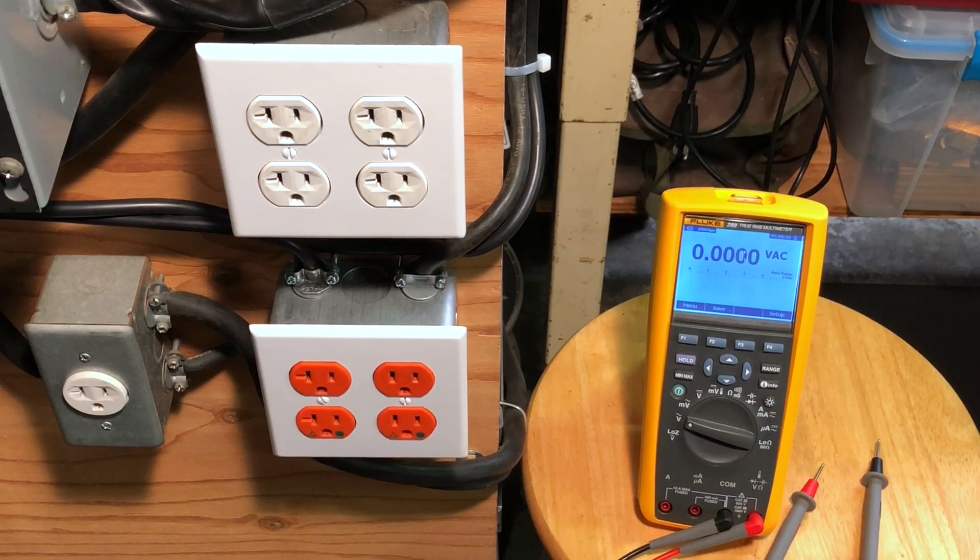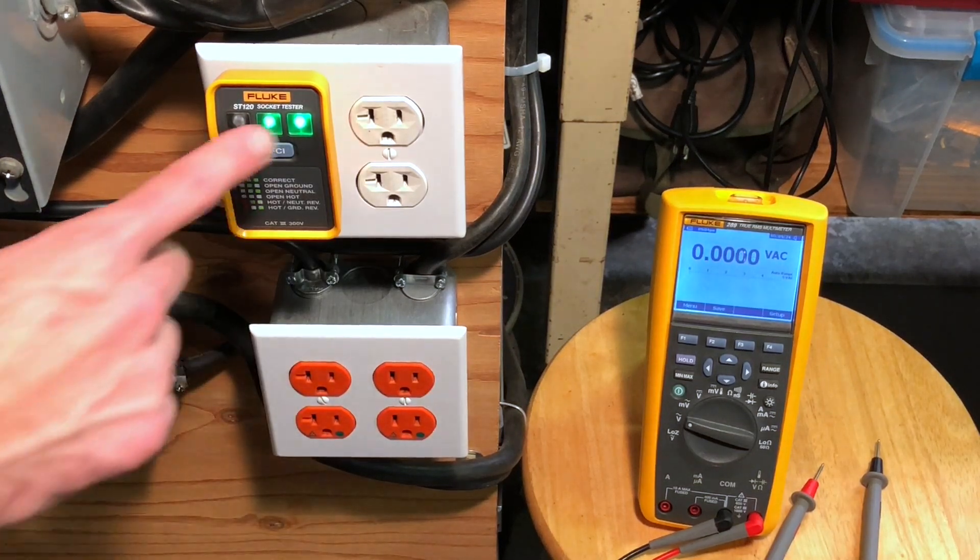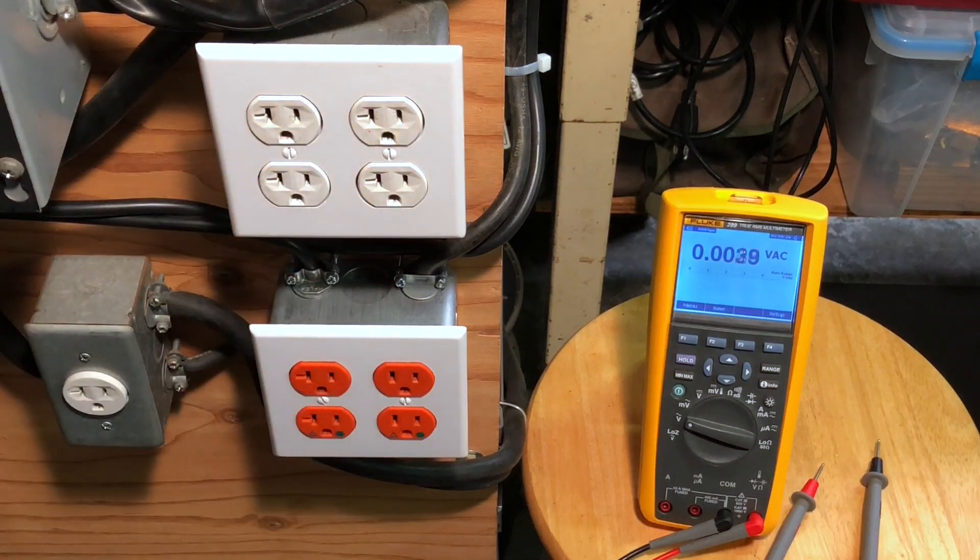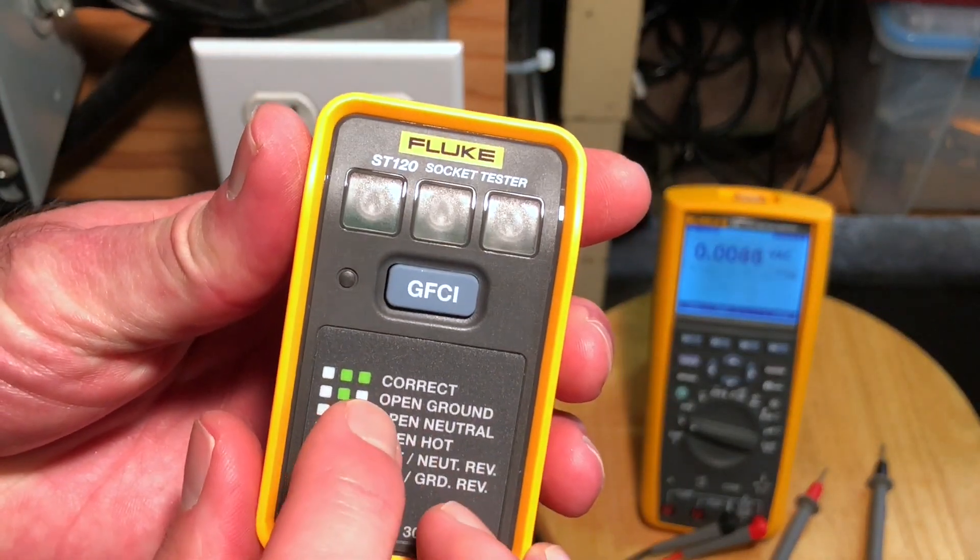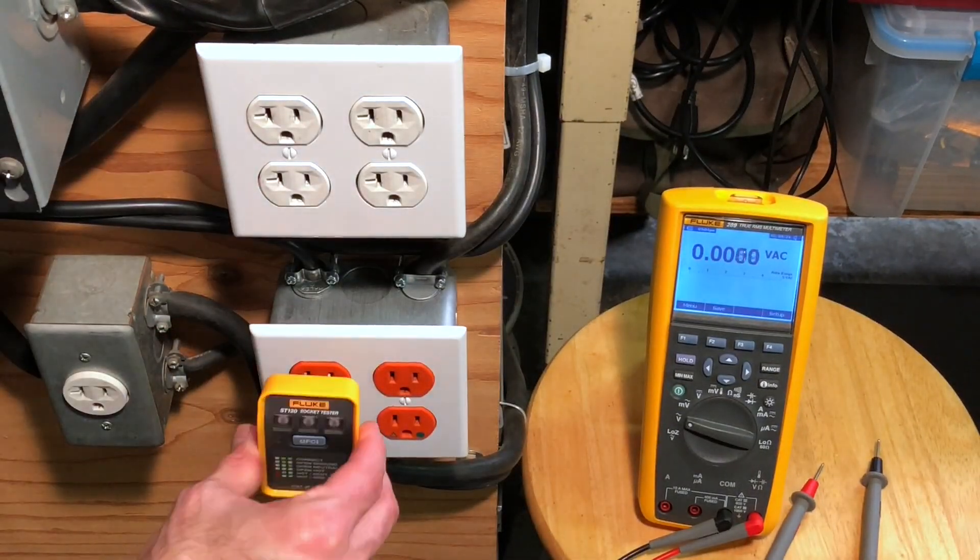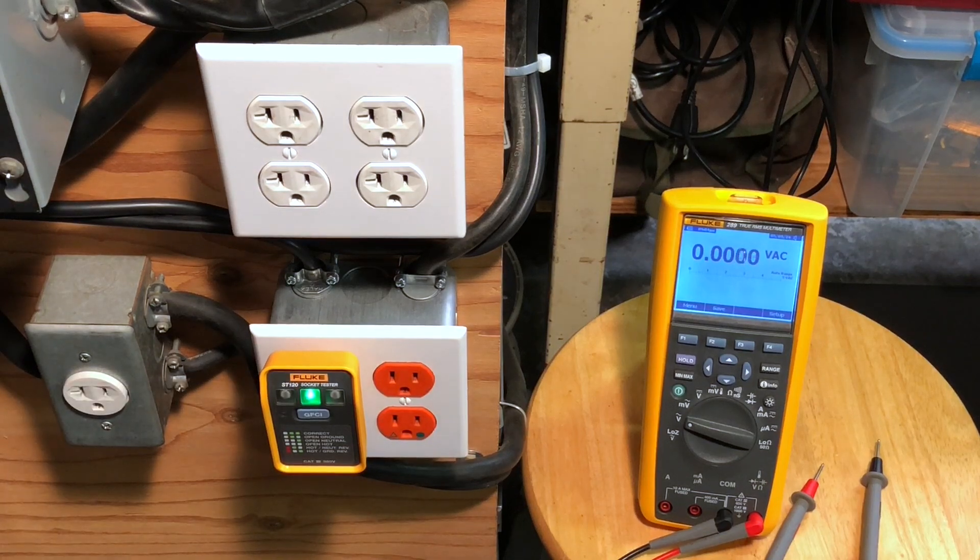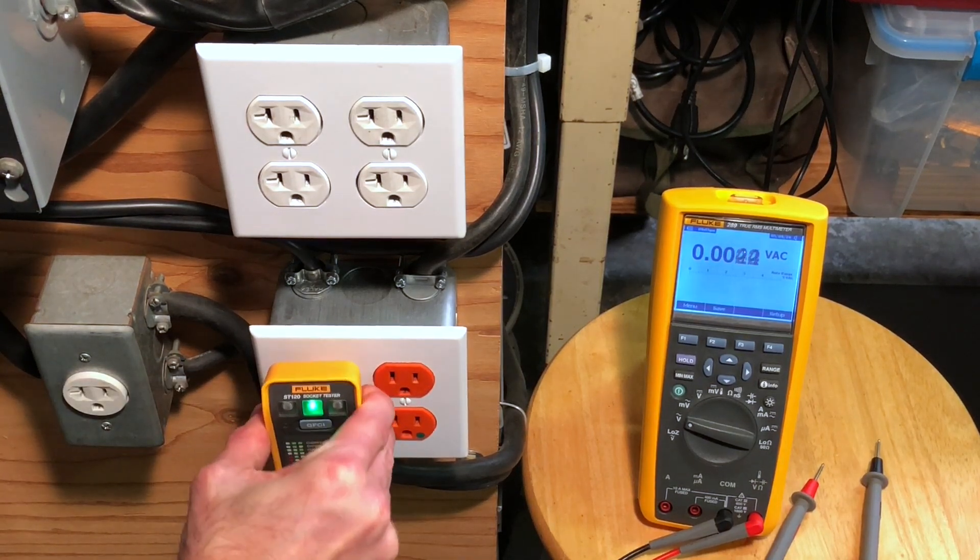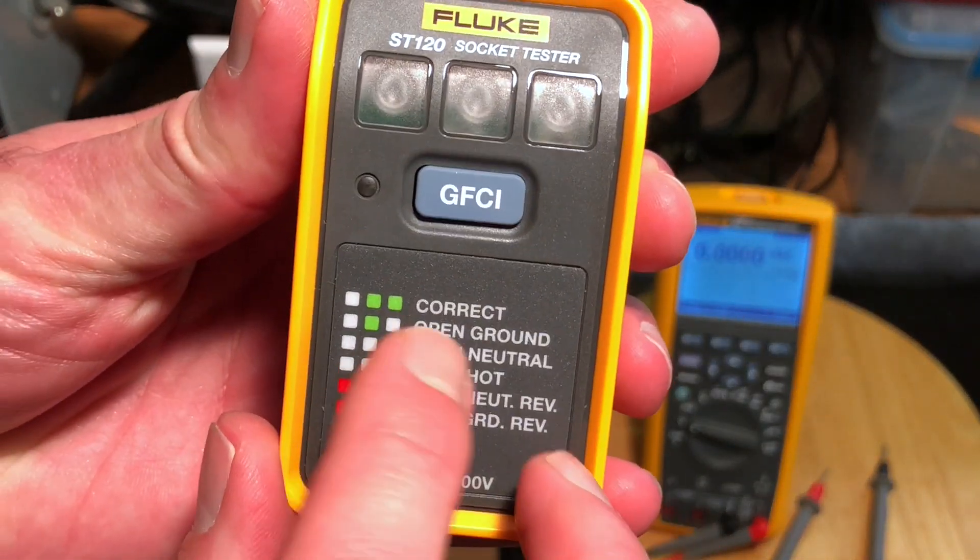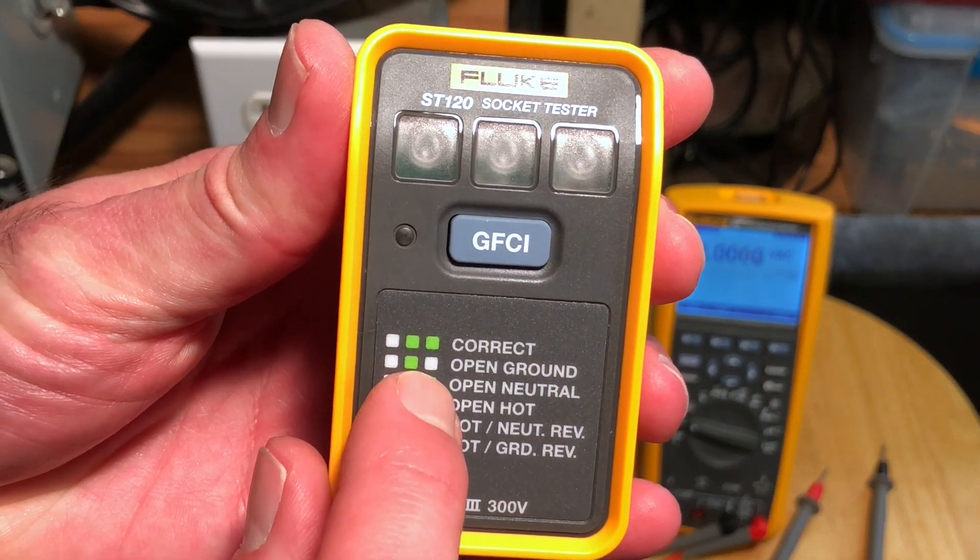Let's plug that in. You can see these are all energized. Down here, same thing, isolation transformer is on. This outlet here is part of an AC power source, a completely different piece of equipment. I have my outlet tester. This will just confirm the wiring configuration. If I plug that in, you can see those two green lights are on and this light is off. If we take a look at the chart, two green lights means correct wiring, no issues. If I plug it into the isolation transformer, there's just one green light that turns on. That one green light in the center means there is an open ground, and that's exactly what we have.